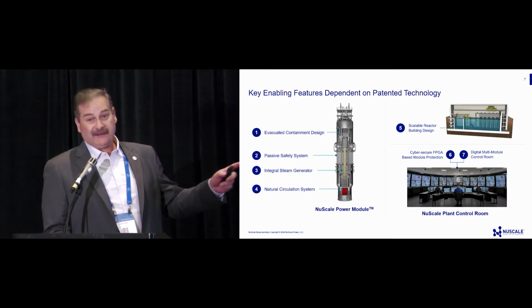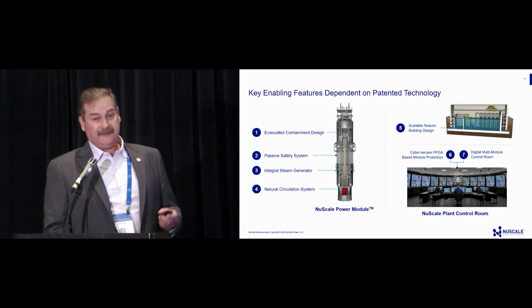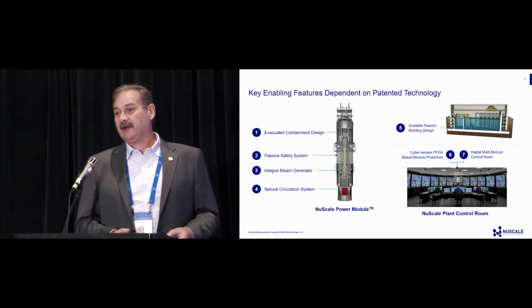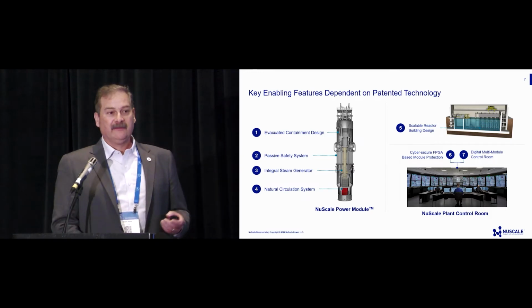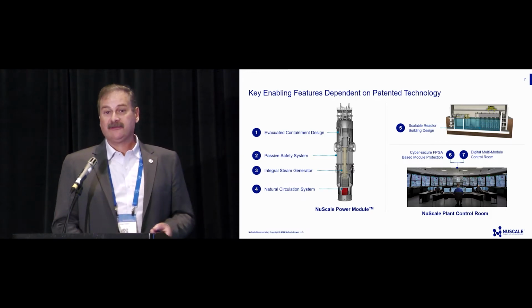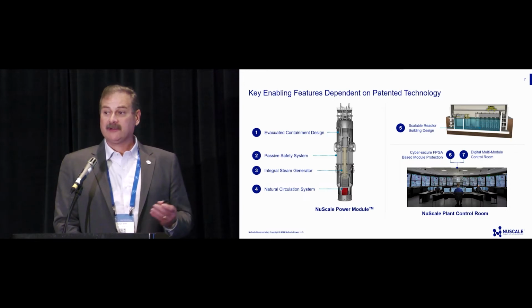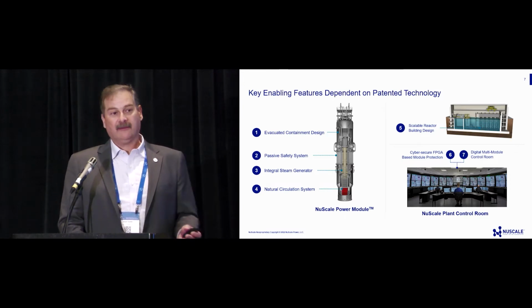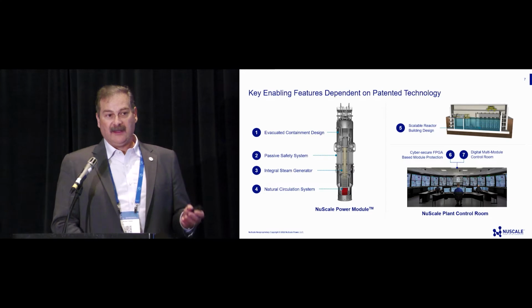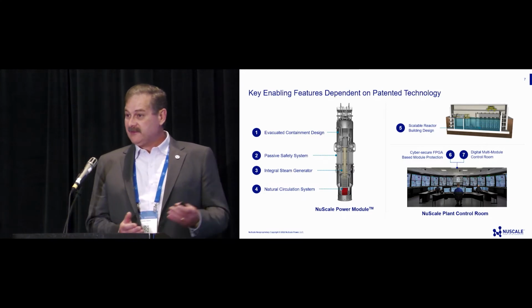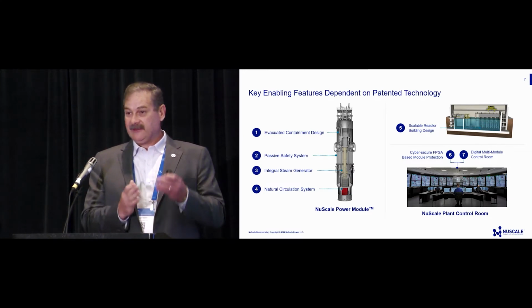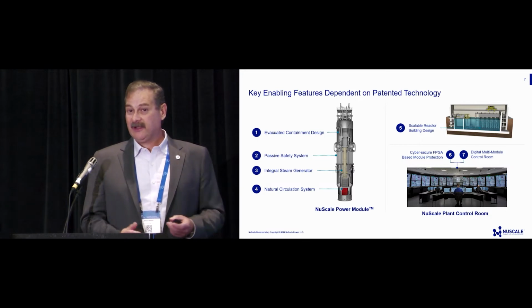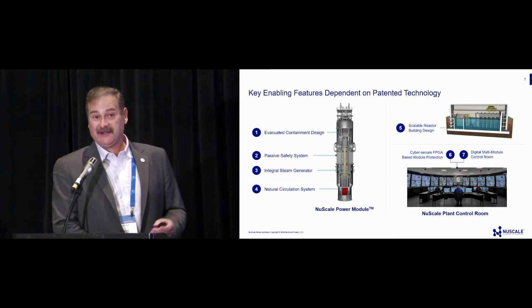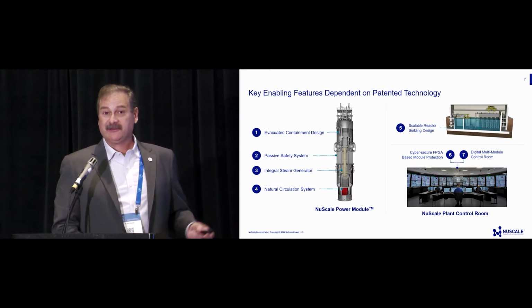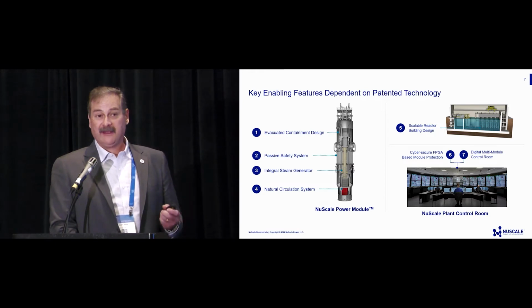One unique thing, I'll go back to number 4, the reactor coolant system, the water that flows around the reactor. The propulsion of that is all natural circulation. So there is no electric pumps that pump the water around through the primary. It's just as the water heats up and its density goes down, it rises, and that creates the flow. And then it gets cooled off by the steam generator, and it falls back down and recirculates around. So that's at power and shut down.